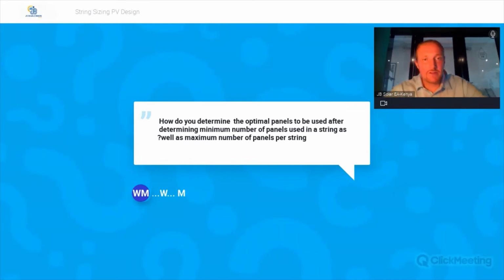How do you determine the optimal panels to be used after determining the minimum number of panels used in a string as well as the maximum number of panels per string? Okay, so the string sizing tool shows you there. It shows you the answer. It shows you the optimum number.